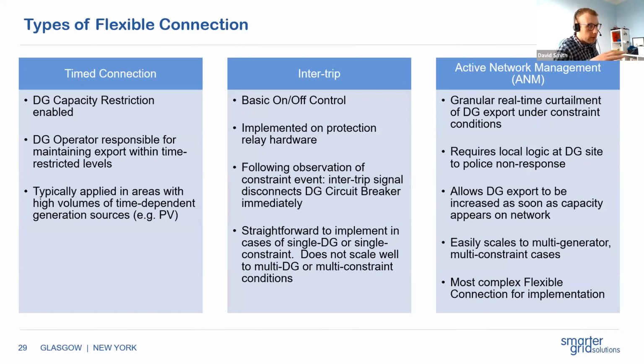There tend to be three mechanisms in the UK historically for managing this type of flexible connection. The first is timed connections, where there are predefined times when generation has to turn down. For example, you might work out that in summer, a wind farm can't generate at the same level, so it would have a reduced set point in summer. That does make quite a wide sweeping assumption.